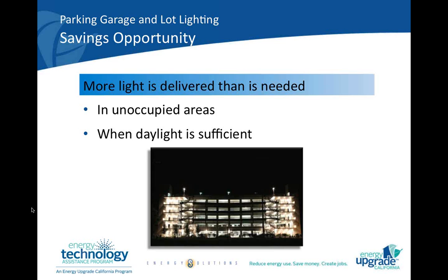So you can have a scenario where, when no occupants are sensed in the area, the fixtures will operate at a lower wattage and a slightly lower light level that still meets the safety needs of the space, but is slightly lower than what would be a comfortable level when patrons are present. But then when occupants are actually sensed, the fixtures will turn to their full power output before the patron actually enters that area that the fixture lights up. Next slide, please.